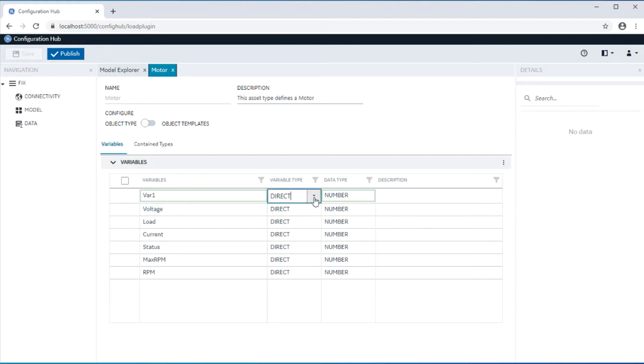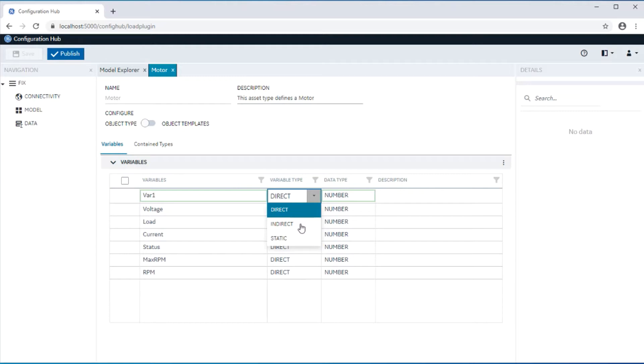Direct variables are created as IFIX tags when this particular type is instantiated to create an asset instance. Indirect variables are not created as IFIX tags, but rather are referenced against an existing IFIX tag. So the model can be paired with an existing flat IFIX tag database through this mechanism.